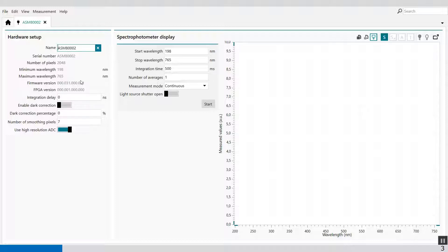Then we see the number of smoothing pixels — an input field which can be used to specify the number of pixels used in the smoothing algorithm. When this value is set to 0, no smoothing is used. The optimal value depends on the fiber diameter, pixel size, and the type of spectrophotometer. The Autolab setup uses 200 micrometers of optical fiber diameter, which corresponds to a number of smoothing pixels of 7. I put 7 as the number of smoothing pixels in my case.